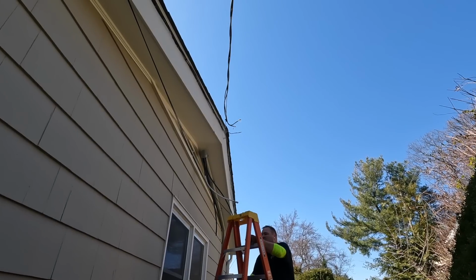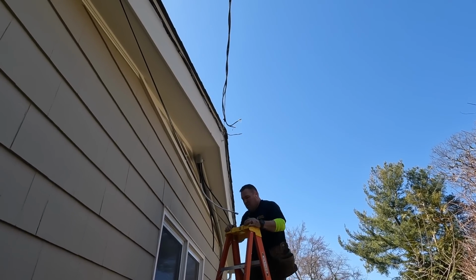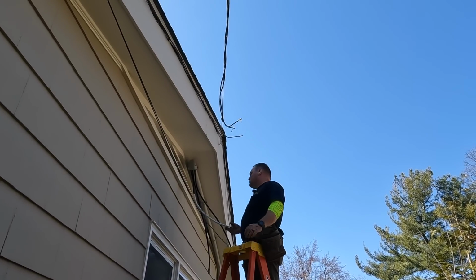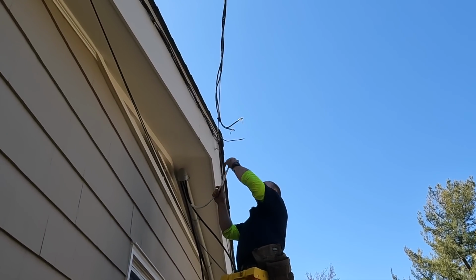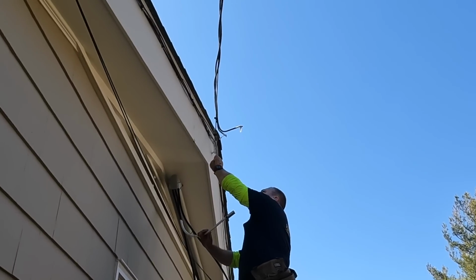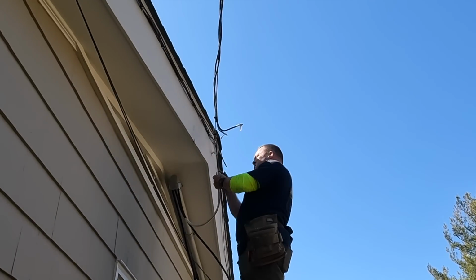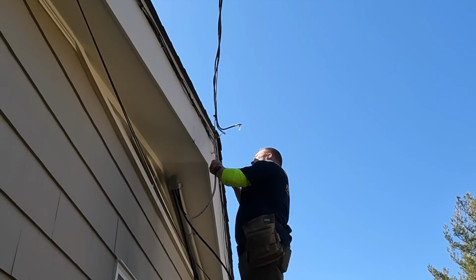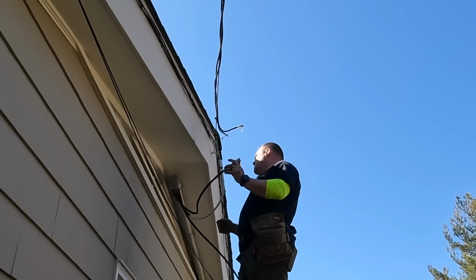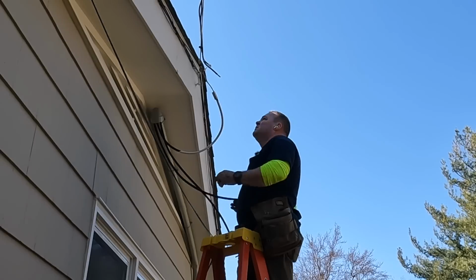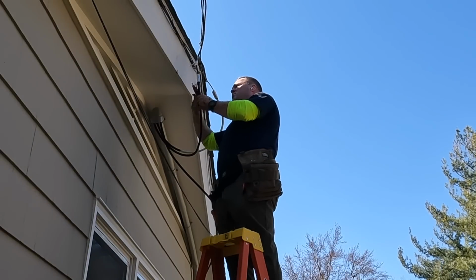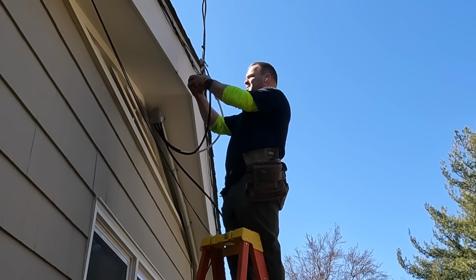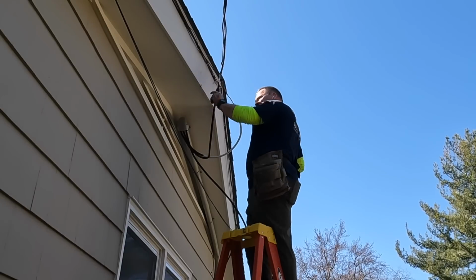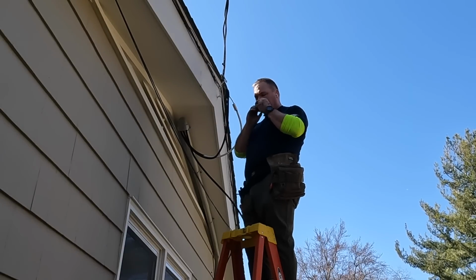All right, so here I am feeding my riser cable, or riser service entrance conductors, up to the weather head, and I'm ready to what we call bug in. Now this particular neutral was broken in a couple spots, so once we get the inspection, we'll call JCP&L and have them come back and maybe even draw a new supply over to this weather head.